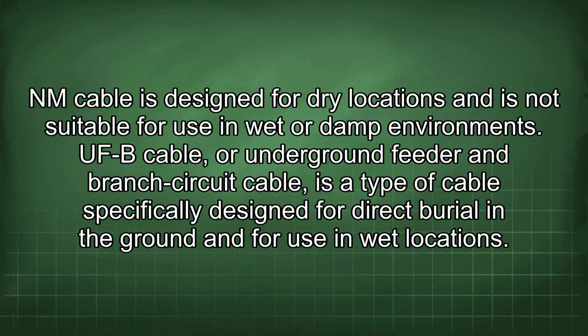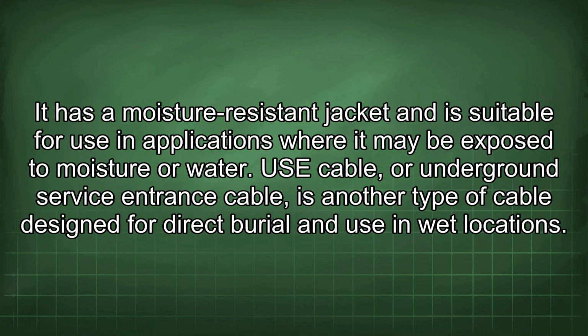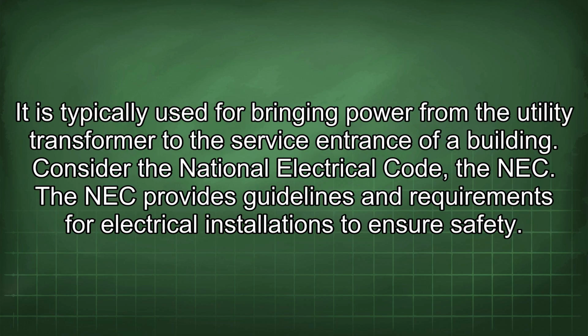UF-B cable, or underground feeder and branch circuit cable, is a type of cable specifically designed for direct burial in the ground and for use in wet locations. It has a moisture-resistant jacket and is suitable for use in applications where it may be exposed to moisture or water. USE cable, or underground service entrance cable, is another type of cable designed for direct burial and use in wet locations. It is typically used for bringing power from the utility transformer to the service entrance of a building.